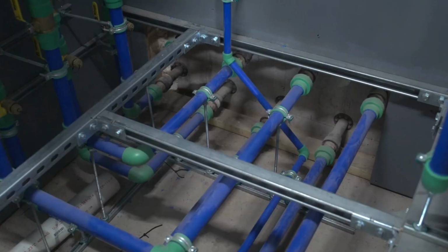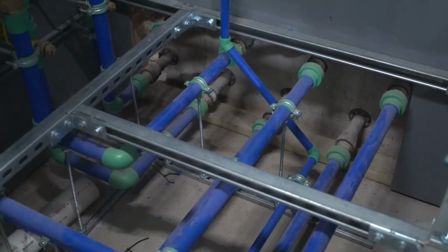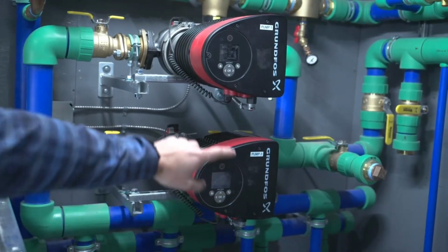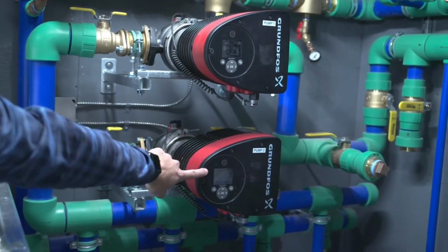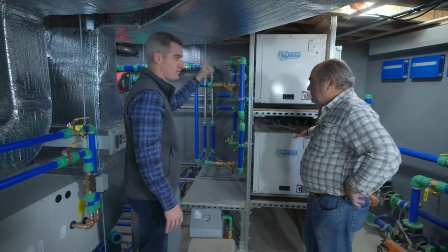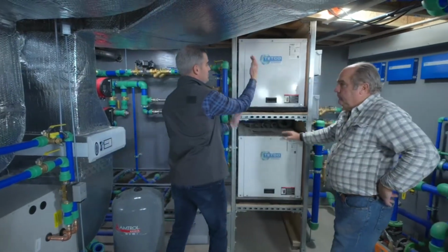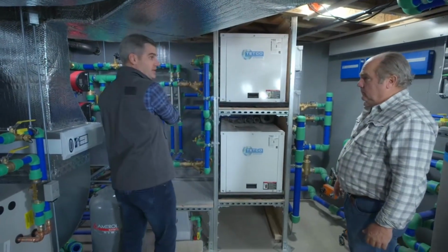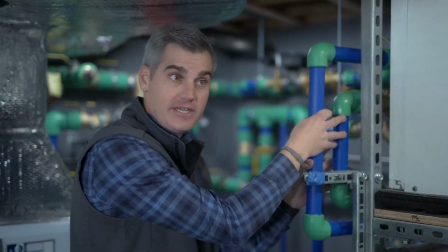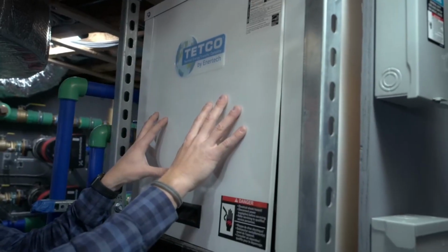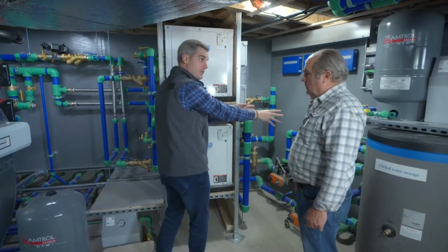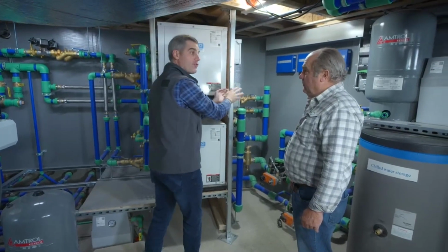So this is where the geopiping starts, right? So here's the 4 supplies and the 4 returns coming through the foundation wall. They're connected to these circular pumps. Super efficient pumps. And this circulator pump is going to be on the entire geo loop, right? So it communicates from the geo heat pumps to the geo field. This is 50 degrees on this side, and the heat pump elevates it to 120 degrees to heat the building, or it can be cooled to 45 degrees to cool the building.